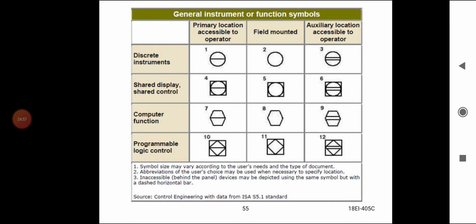Primary location accessible to the operator. Field mounted and auxiliary location accessible to the operator. If it is a discrete instrument, a circle with a line inside, it is a primary location accessible to the operator. If it is field mounted, just a circle. Auxiliary location accessible to the operator, a double line inside the balloon. Shared display, a rectangular box inside the circle. No line inside means field mounted. Auxiliary location is a double line inside.